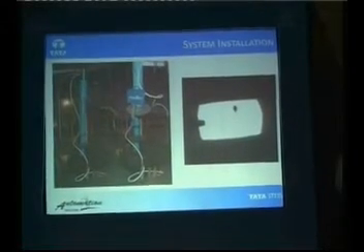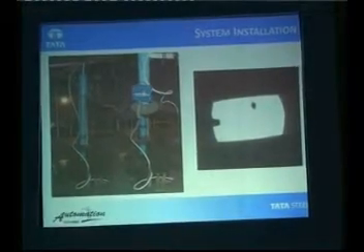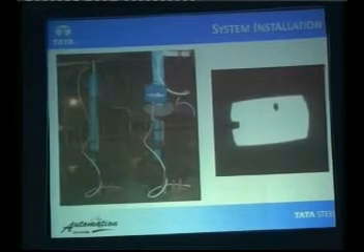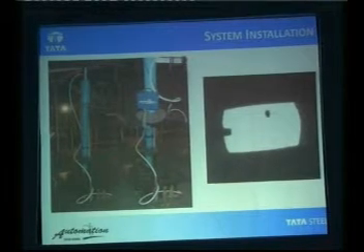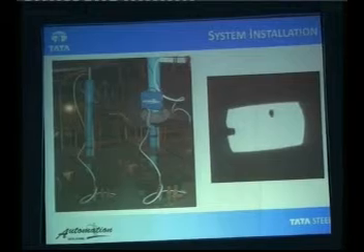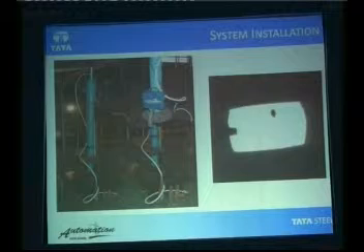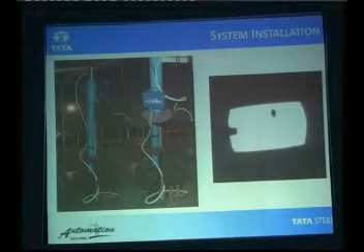This is the system installation, which is done in the measuring house of the roughing mill. We've used a pinhole technology where there is only a small hole of about 3 to 5 mm, and the camera is placed in a 2 meter long tube. We have to measure the whole transfer bar through that pinhole. The major advantage is that we do not allow any dust or water particles to come in, and we are protected against the temperature.